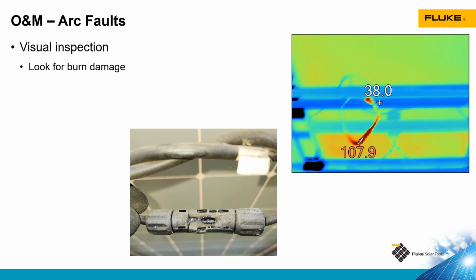Finding all arc faults is notoriously hard. I can do visual inspection looking for burn damage. In the example we see here, the picture on the left, I believe that this started as a series arc fault in this connector. You can see there's a little bit of a gap between the positive and negative side of the connectors, and that should not be there. They should be butted right up against each other. I think that this was arcing in this series connector and started to melt it.